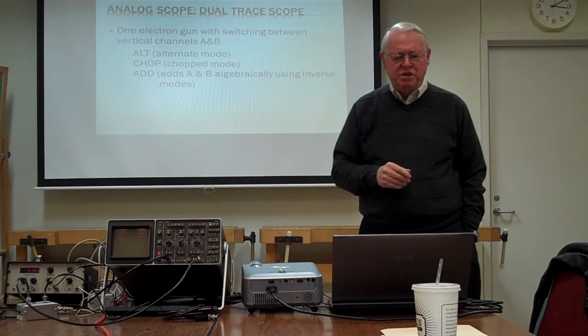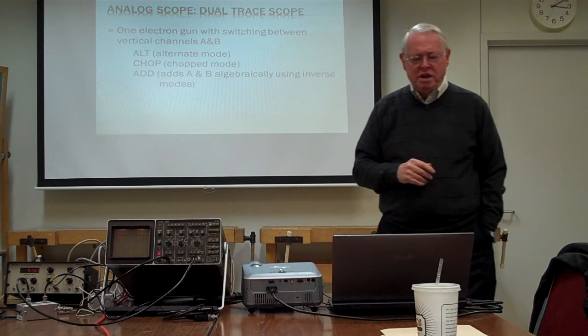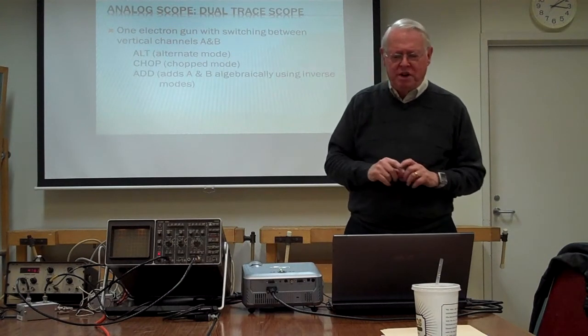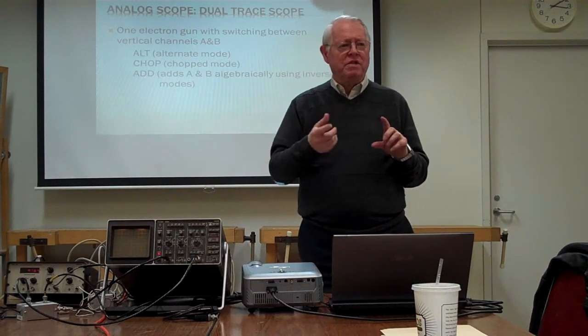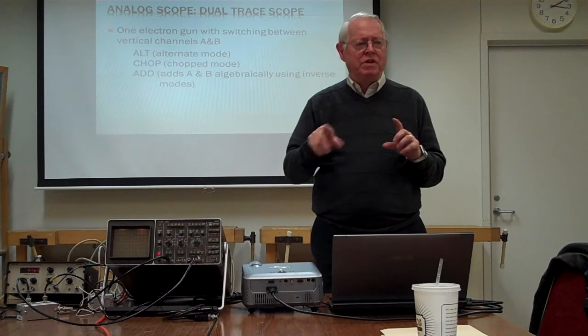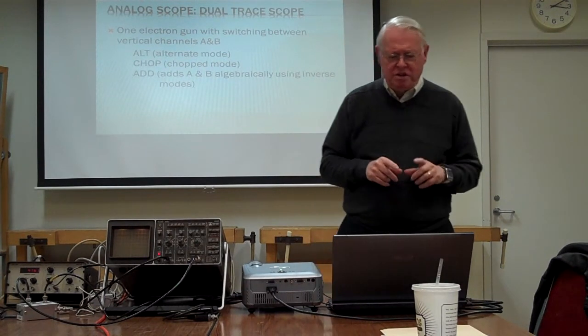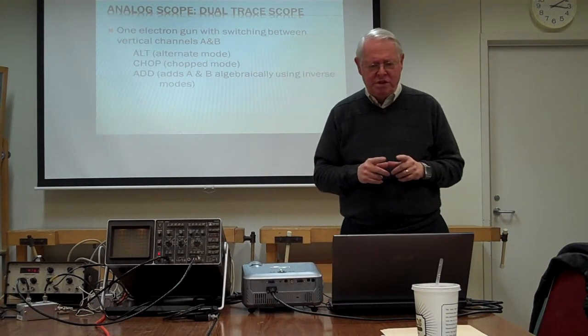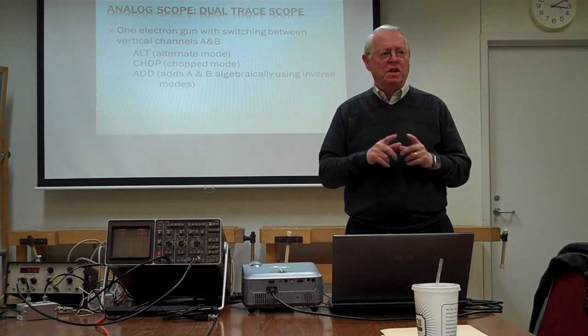And then another feature is that you can also add A and B algebraically. So if you've got two signals you're trying to balance, you put one in inverted, which is another function of the channel A and B vertical inputs, and you can null one against the other — for instance, comparing a standard to something you're trying to measure.